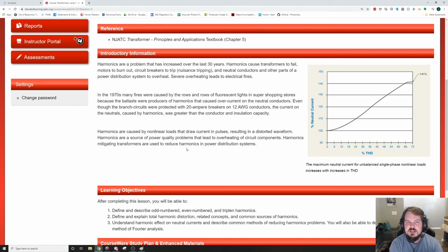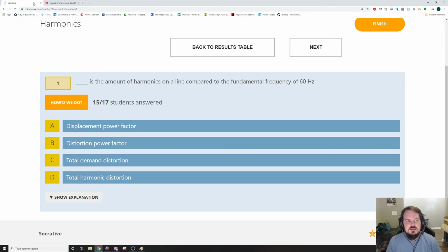But with harmonics, the amperages won't cancel out completely. Say you get 3/4 of the amperage from one line and 3/4 from the other line, well, now you have 150%, or 6/4 if you want to say it that way. You have 150% of the amperage that was supposed to be on the neutral. So now you have too much amperage on your neutral line.